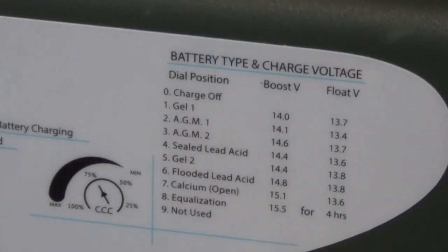This little chart on the exterior cabinet of the inverter indicates different battery styles, but the real important information is it shows your boost voltage and float voltage. I'm using lead acid batteries, and it says 14.8, 13.8, but I actually went to Trojan's website, and for my batteries it runs 14.6 and 13.5. So actually setting number 3, AGM2, is closer to what my manufacturer recommends than what that chart shows. So I went and put it on AGM2 to get my voltages a little closer to what the manufacturer recommends.